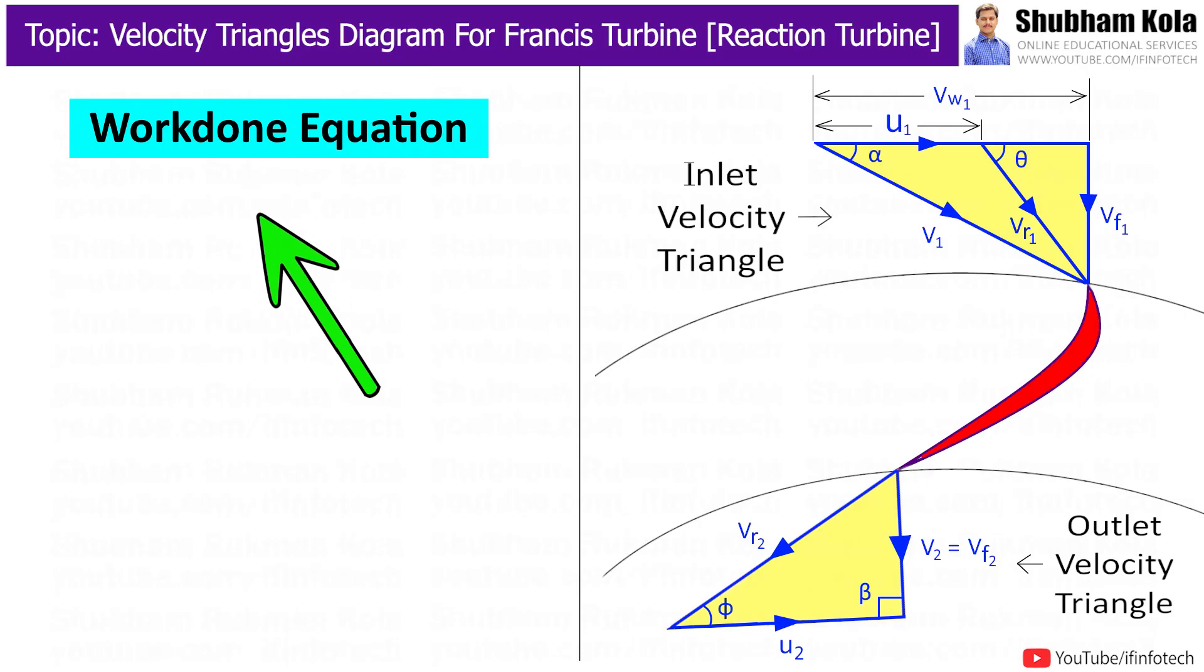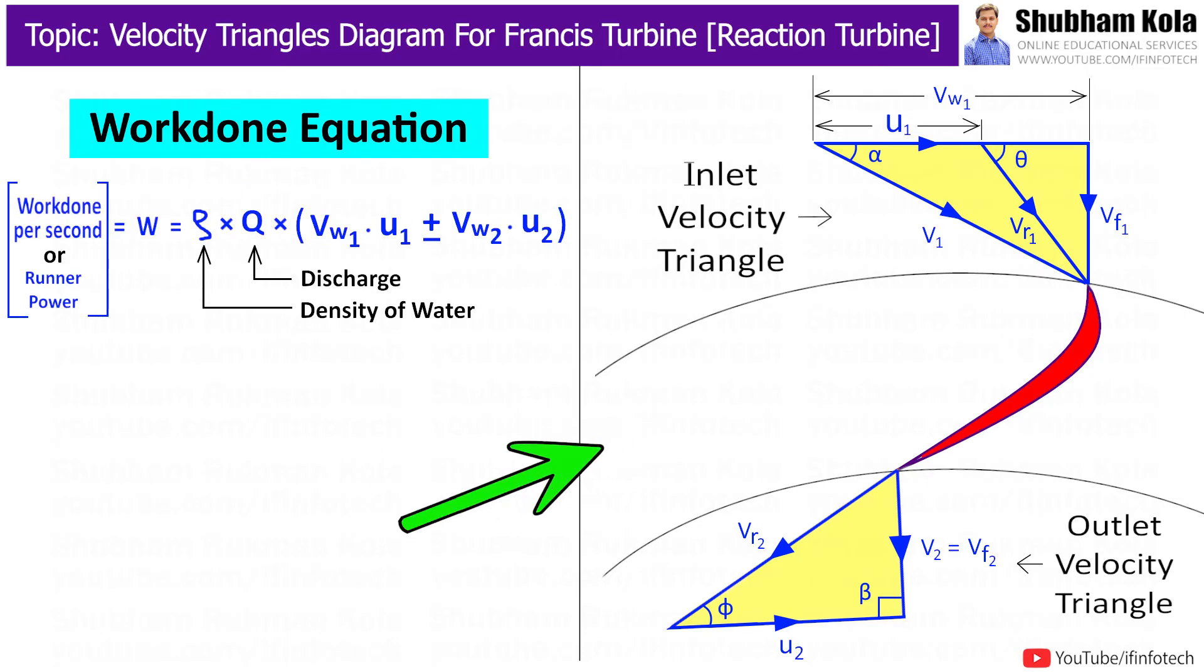Next we will move to the work done equation for Francis turbine. In case of Francis turbine, work done per second which can be written from Euler's momentum equation where q is discharge through runner in m3 per second which is area multiplied by velocity. Here positive sign is taken when beta is less than 90 degrees and negative sign is taken when beta is more than 90 degrees.